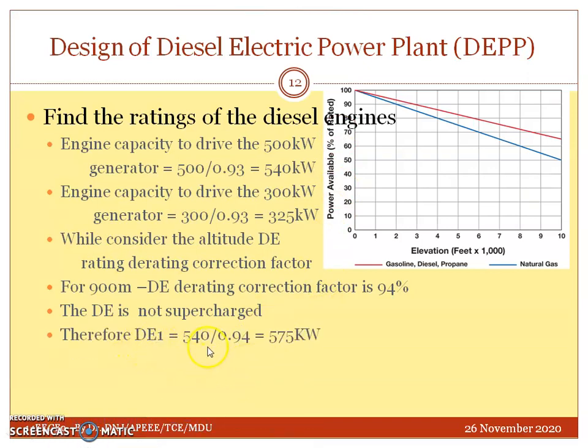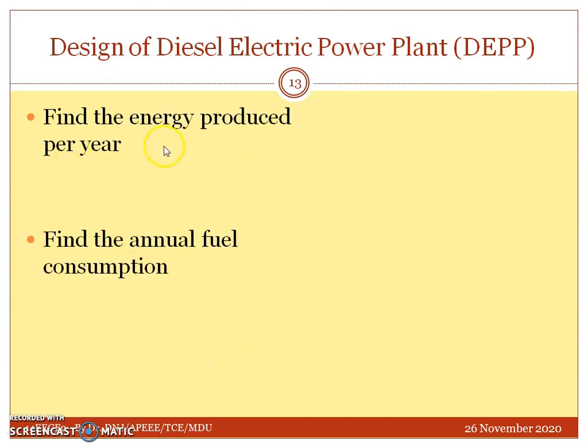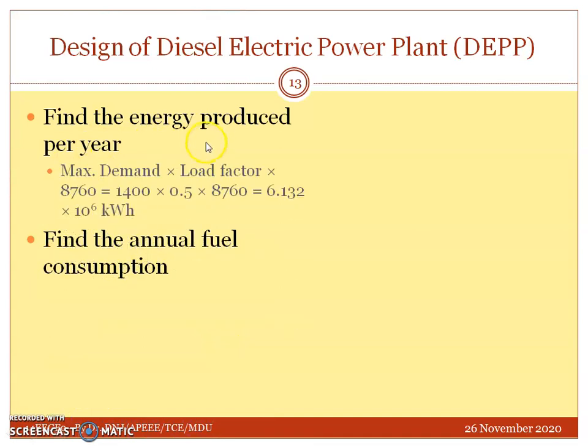When this altitude correction is incorporated, the first diesel engine requirement becomes 575 kilowatt and the second machine requires 346 kilowatt. Next, energy produced per year is calculated as maximum demand multiplied by load factor multiplied by total hours in a year, giving 6.132 × 10^6 kilowatt-hours.